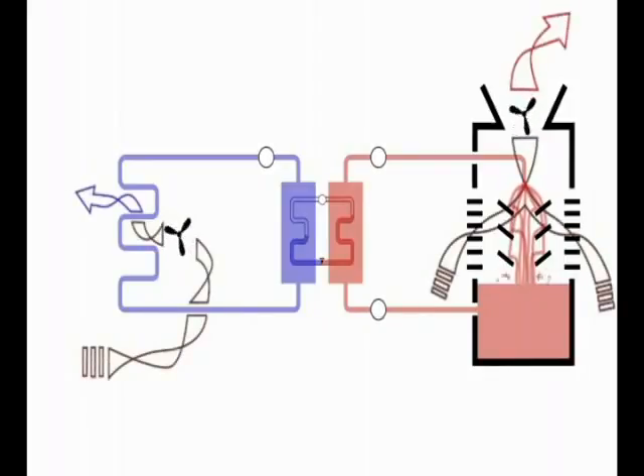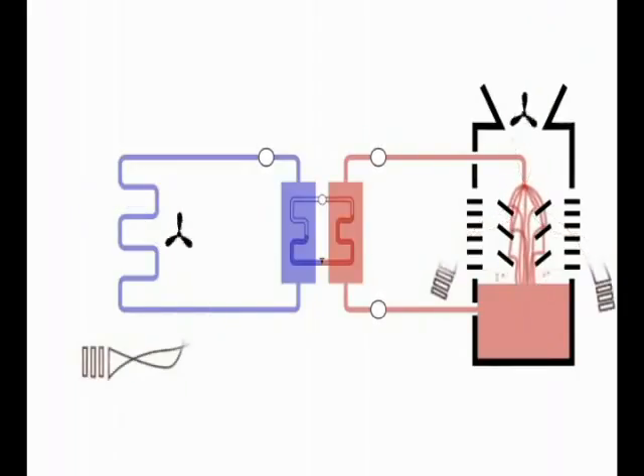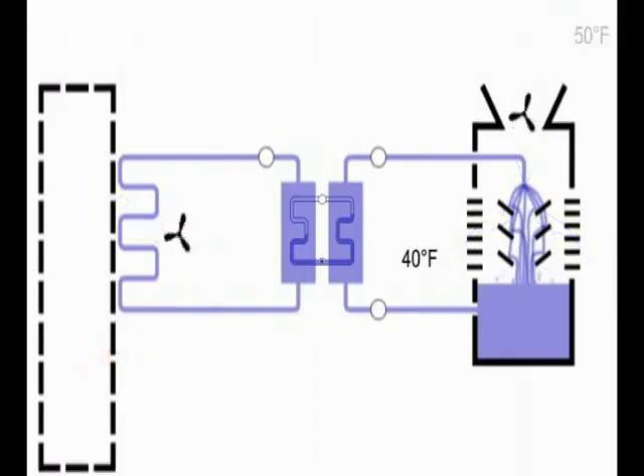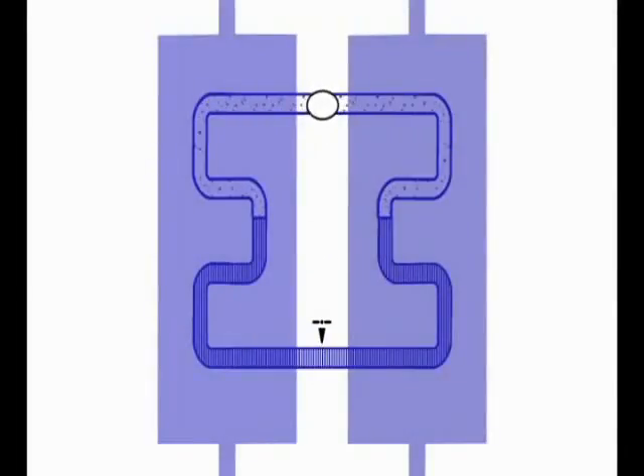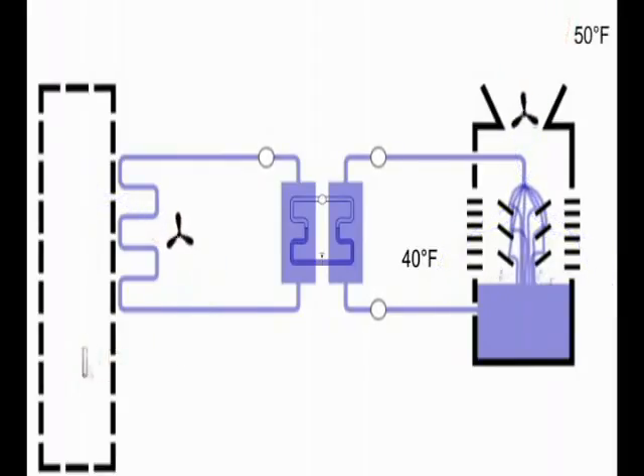Here, we'll review two methods of doing this, so-called free cooling: water side economizers and air side economizers. In a water side economizer mode, cold air cools, and it really cools because it's winter, the water in the cooling tower. That cold water moves to the condenser side of the chiller and cools the coolant. The expansion valve opens, and this is important. The cooled coolant moves to the evaporator without fighting its way through the expansion valve. And there in the evaporator, it cools the chilled water. We've bypassed the compression refrigeration process entirely and still created chilled water for delivery in the standard way.